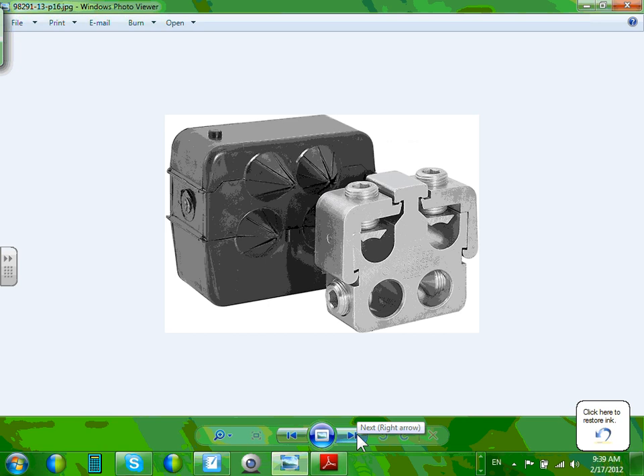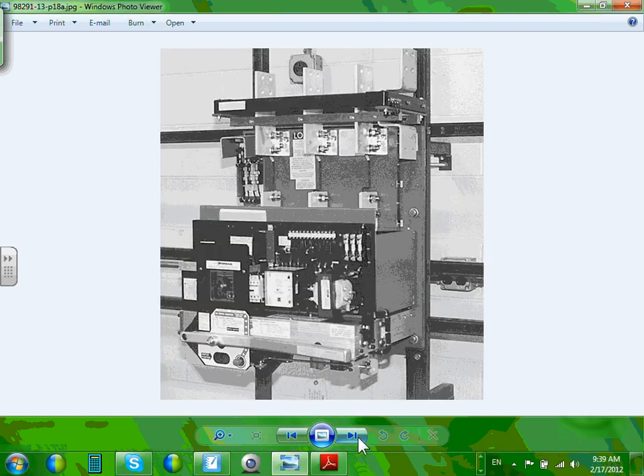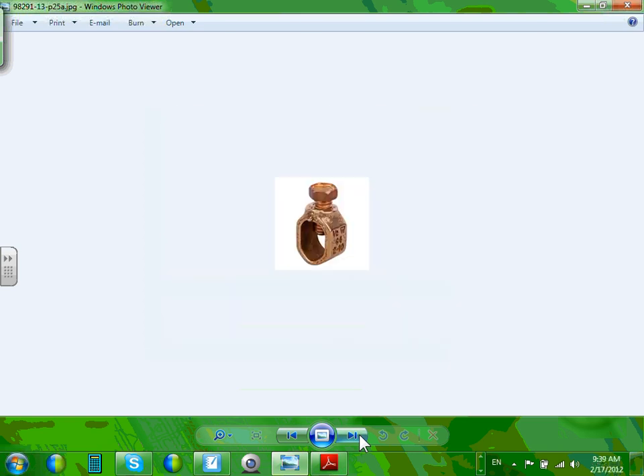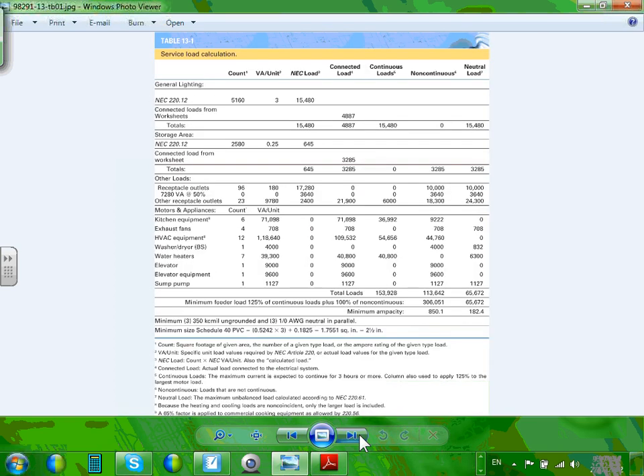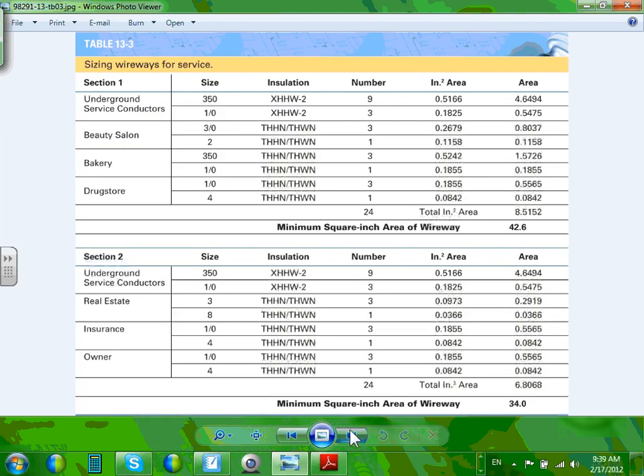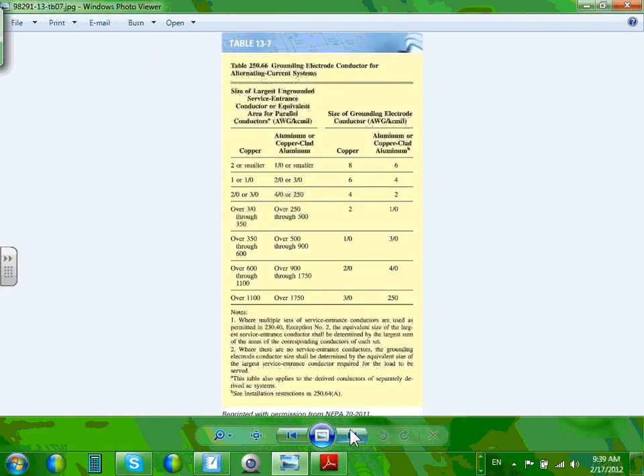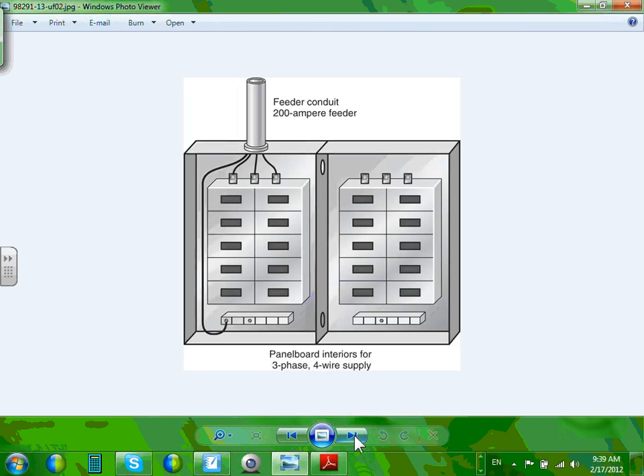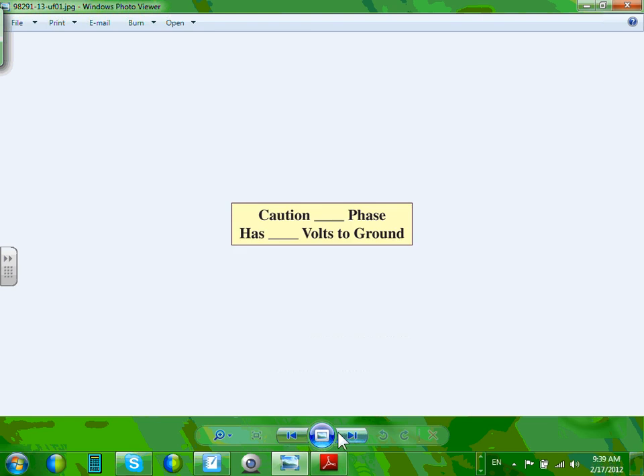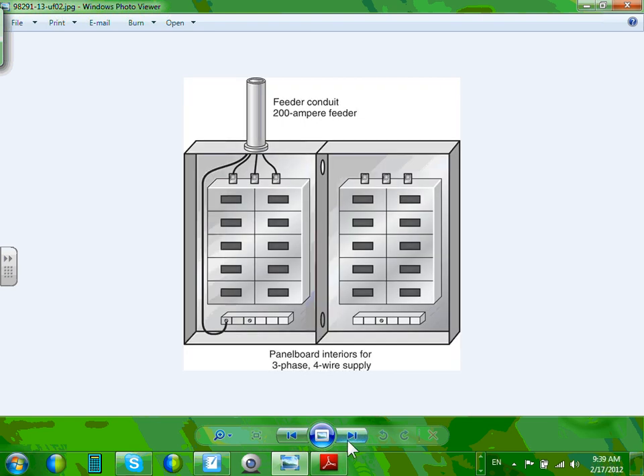A couple of CTs, I believe. And bonding, a couple of bonding hardware that they have here. Load calculation: we did a load calculation, so I'm not going to bore you with these. This is the table that we size the grounding electrode conductor, main bonding jumper and system bonding jumper. A couple of things about the panels that you guys have to know. Your panel has to be labeled with the available service short circuit current, and if it's a delta, it has to be labeled with delta. It has to have a directory that identifies the location of all the circuit breakers.